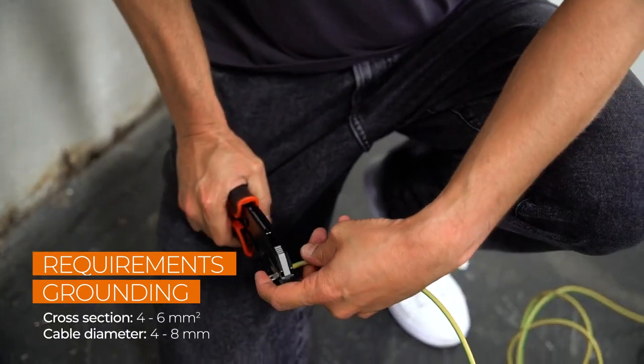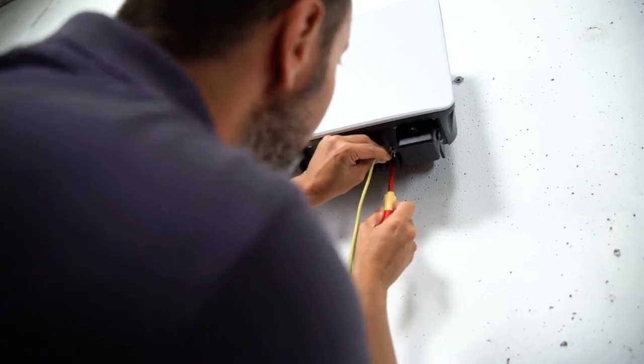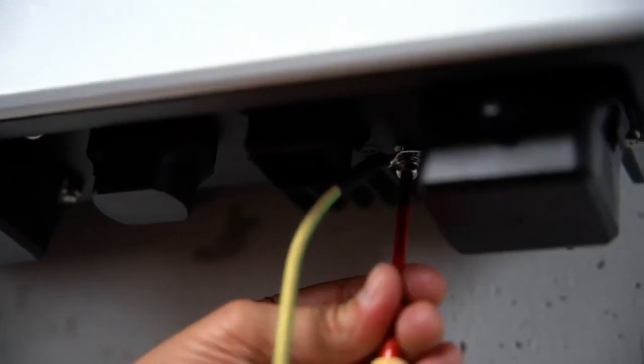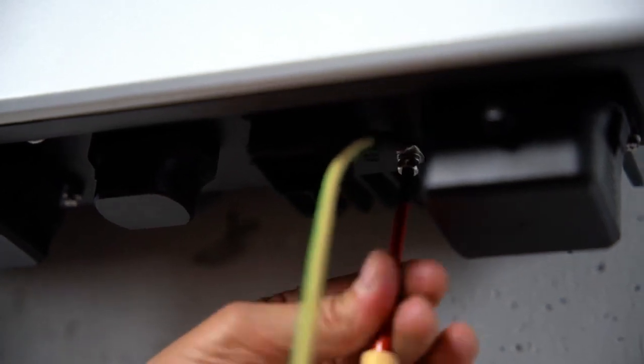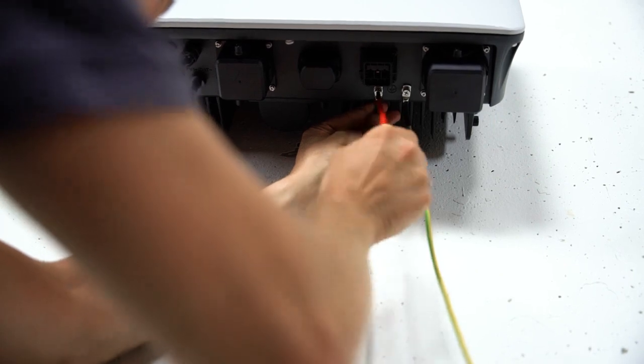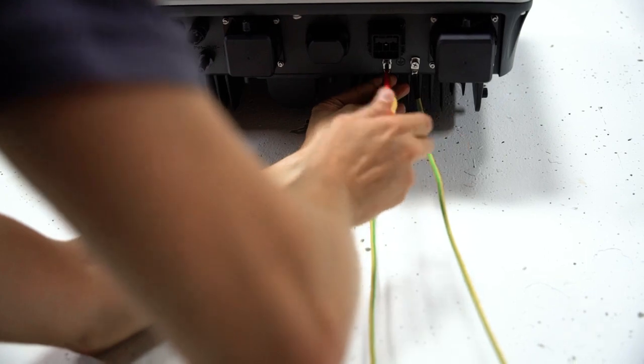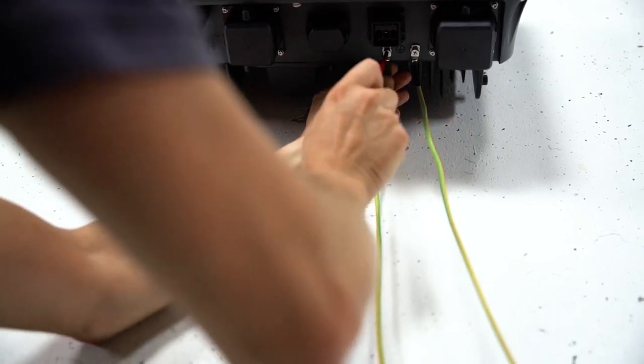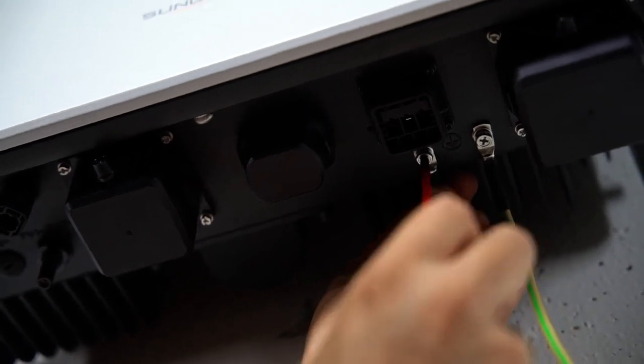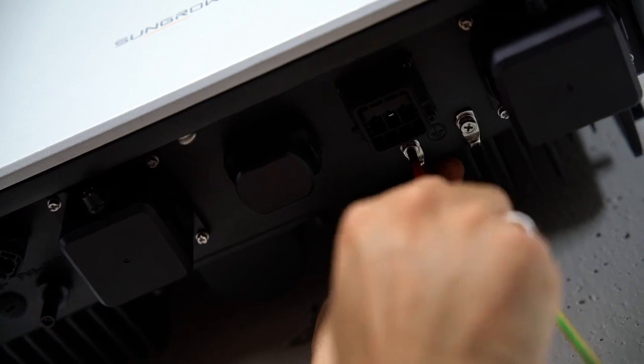In the first step you have to connect the inverter to ground. There are two PE connections at the bottom of the inverter. The one below the backup port will be connected to the grounding of the backup loads. The other one will be connected to the grounding of the battery. Make sure that the chassis of the inverter, the backup load PE and the grid side PE are all connected to the same grounding point. If the grounding connection isn't done properly, it may affect the backup function.